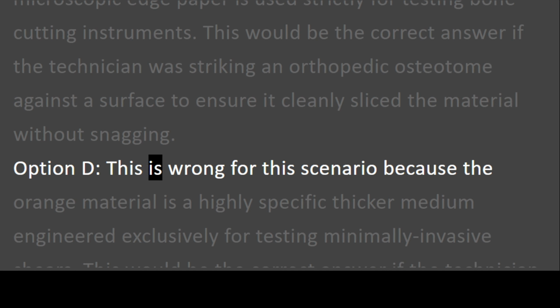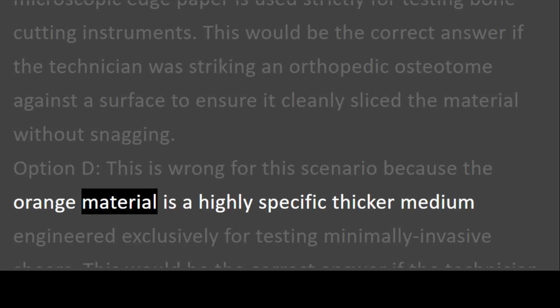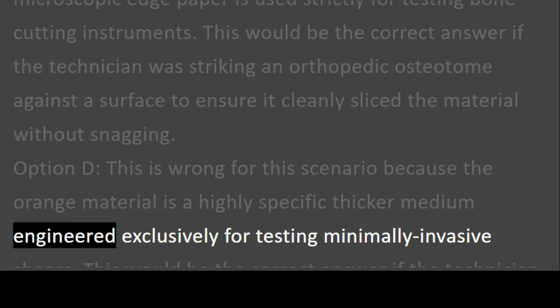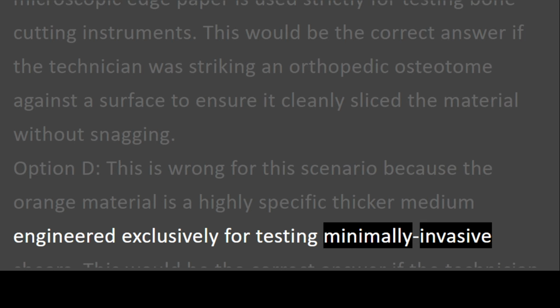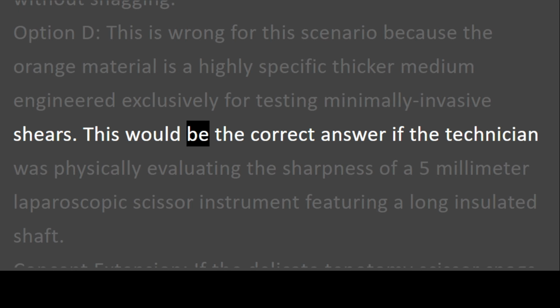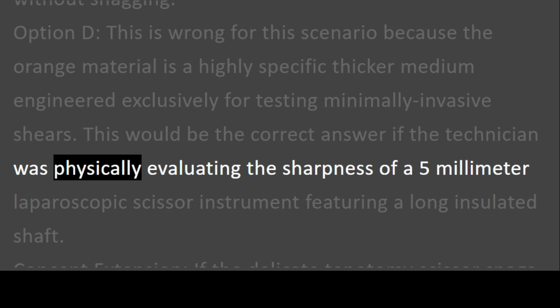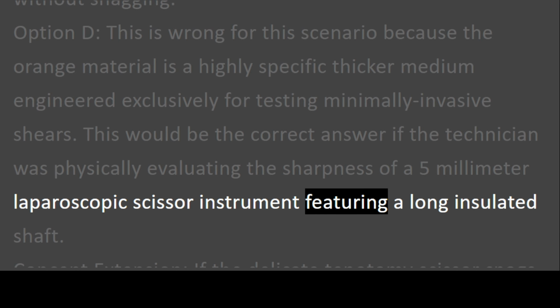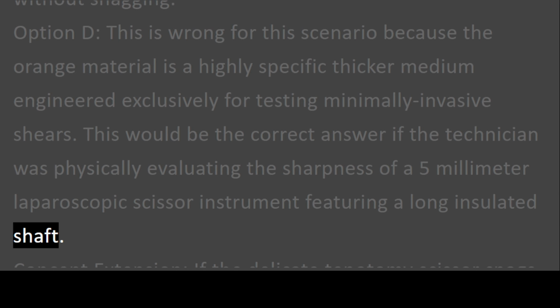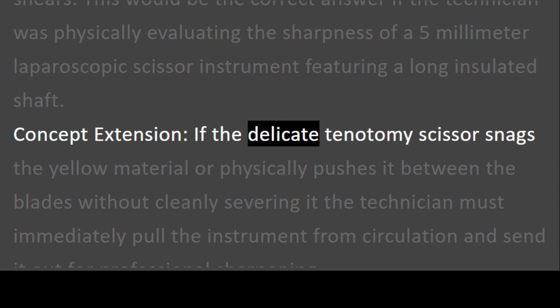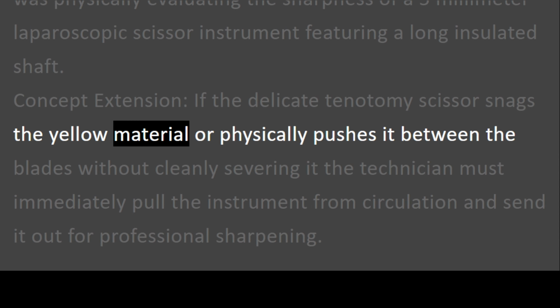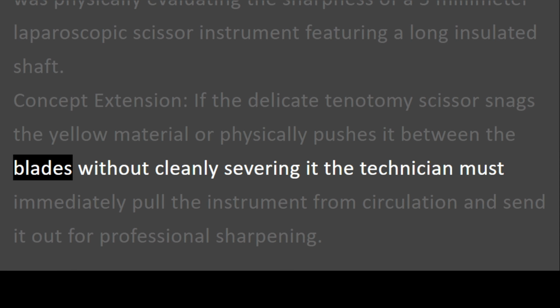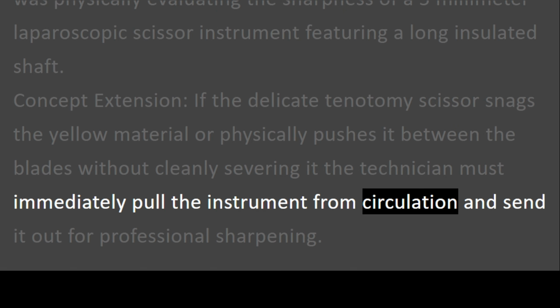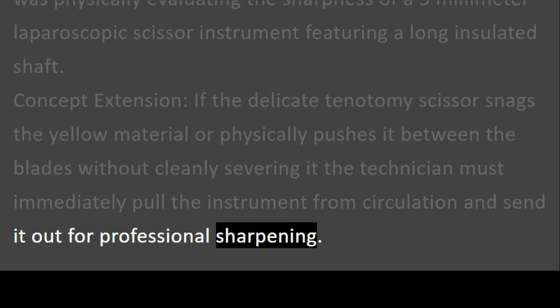Option D. This is wrong for this scenario because the orange material is a highly specific thicker medium engineered exclusively for testing minimally invasive shears. This would be the correct answer if the technician was physically evaluating the sharpness of a 5 mm laparoscopic scissor instrument featuring a long insulated shaft. Concept extension. If the delicate tenotomy scissor snags the yellow material or physically pushes it between the blades without cleanly severing it, the technician must immediately pull the instrument from circulation and send it out for professional sharpening.